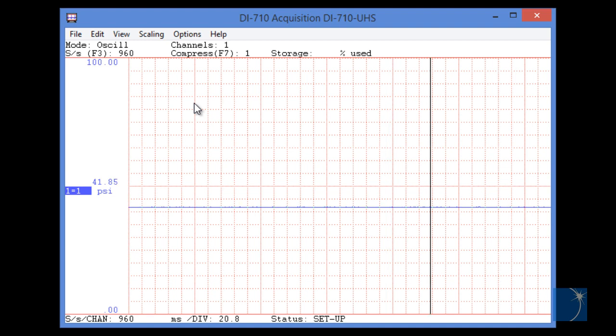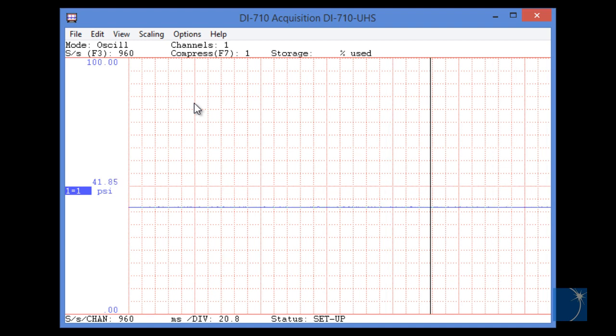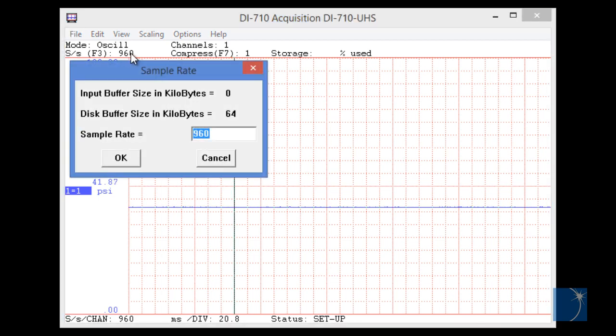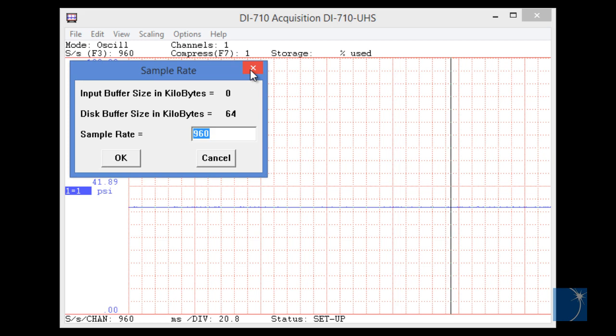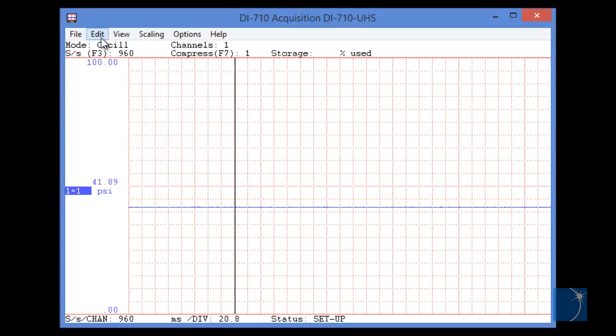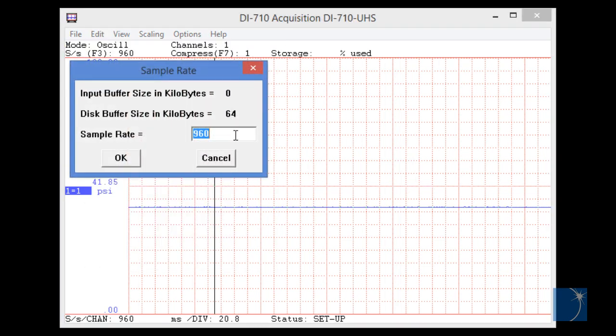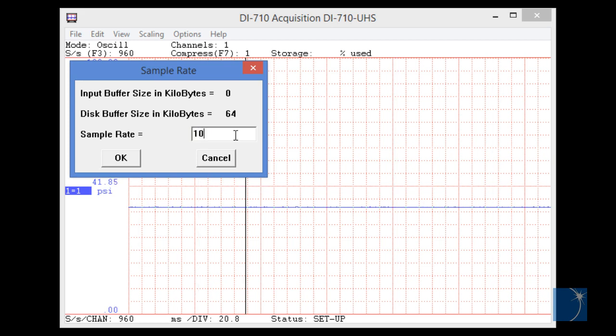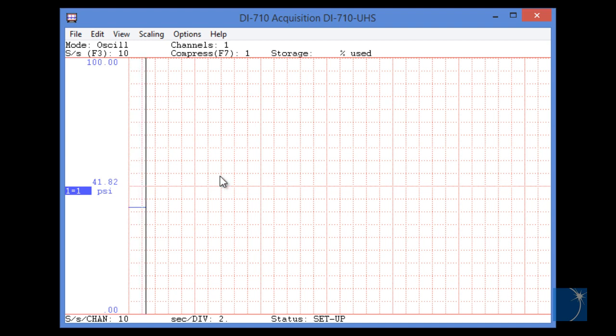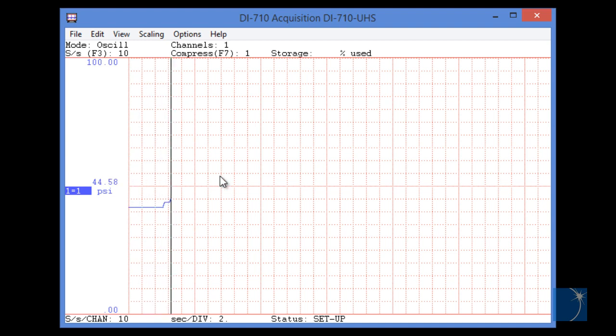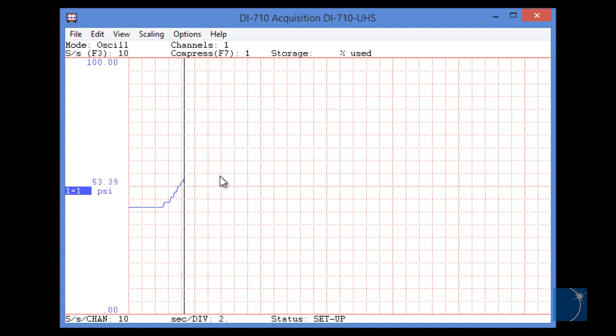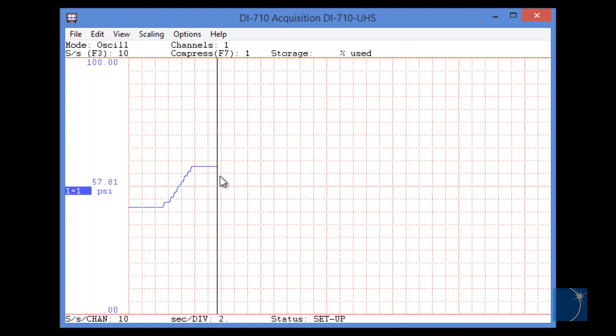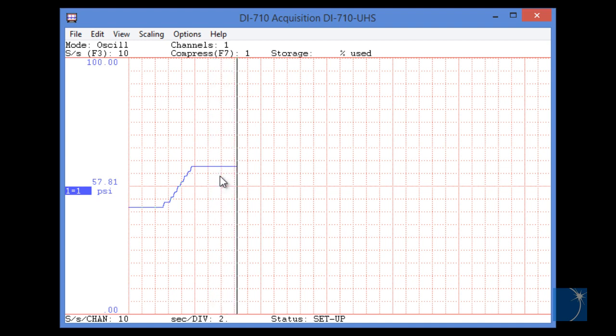Next, we'll need to choose an appropriate sample rate. Since we're dealing with a relatively slow-changing pressure, we'll double-click on the sample rate, in this case 960. Actually, a better way to do this would be to choose Sample Rate from the Edit pull-down menu, and lower the rate to maybe 10 samples a second, which is sufficient for a slowly changing pressure. Your sample rate will vary depending on the signal that you've connected, or the signal that you're acquiring.